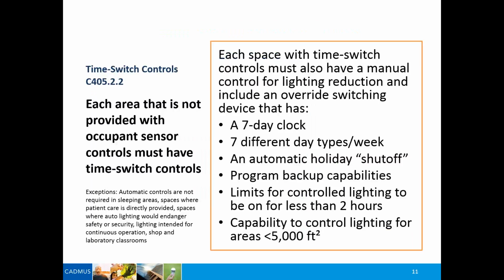So in the 2006 code, you also have a requirement for automatic lighting shutoff that we briefly mentioned. The automatic lighting shutoff control in the 2006 code was either using a time clock, or it was using an occupancy sensor. So the way this code is structured right now, if you're in spaces that are not required to use, that don't have an occupancy sensor, you actually have to have a time clock control to be able to turn the lights off on a scheduled basis.